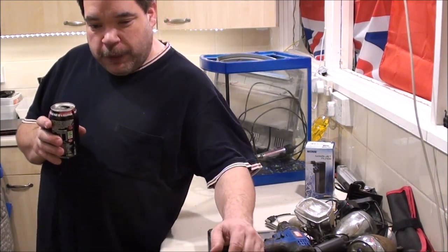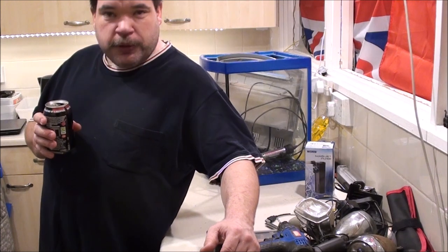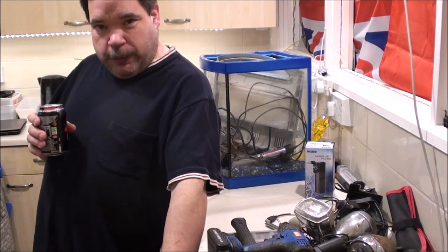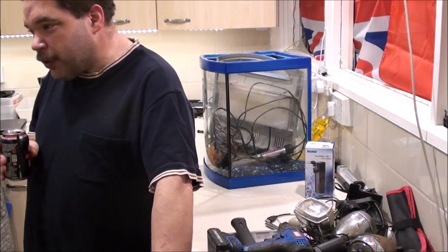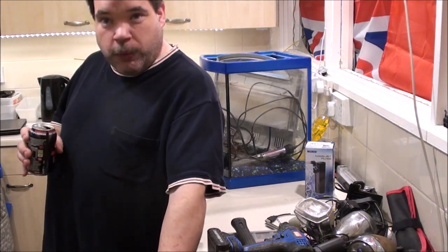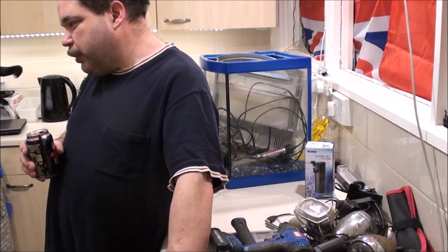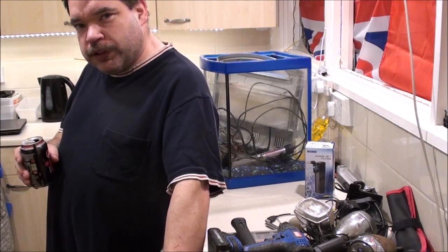It was all small stuff, apart from one job — actually two big jobs. The electrician here Wednesday wants to change my consumer unit, or fuse box if you're old school, because it's overcrowded. He actually found one breaker has four circuits connected to it, and another breaker with three connected to it. Depending on what circuits they are, I personally wouldn't necessarily have a problem with it.